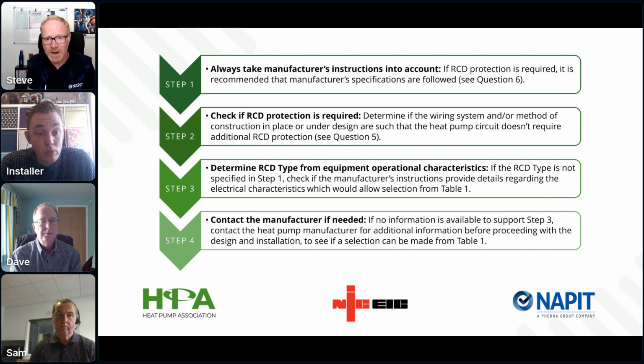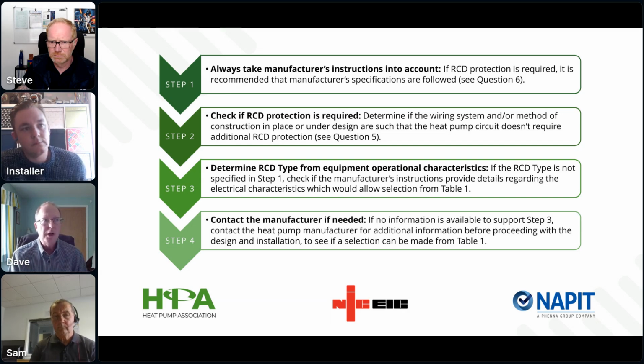So it is looking in the round at the whole picture rather than isolated incidents. But then, Dave, if you go against the MIs, or if the MIs are quite broad, what could then come down the road for you as an installer? I think the key point is the one that was made earlier: the wiring regulations say take them into account. So if you are trying to design out the need for an RCD, then you are taking responsibility for your design decisions, and that may be perfectly correct. But you have to be conscious that you might have to justify the decisions you've made and that you are making the correct choices.